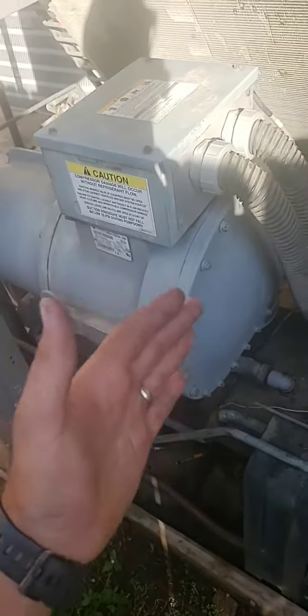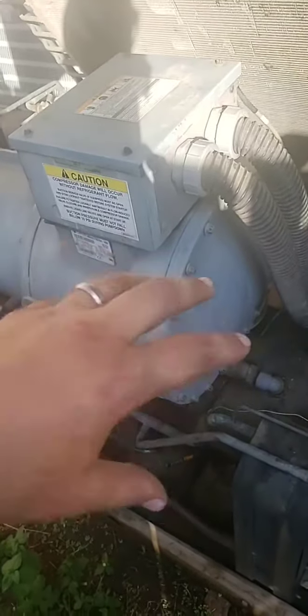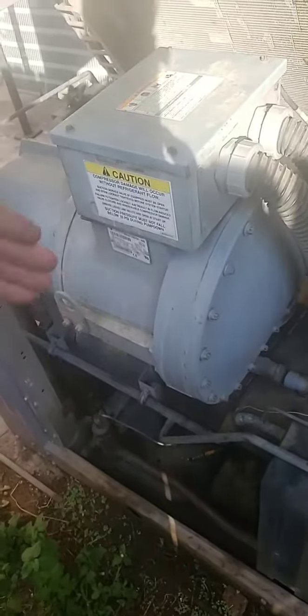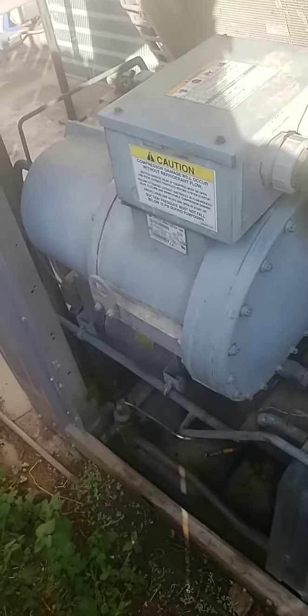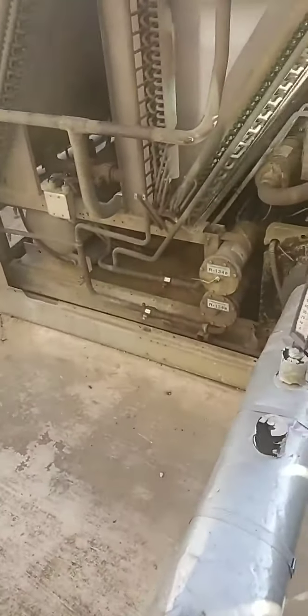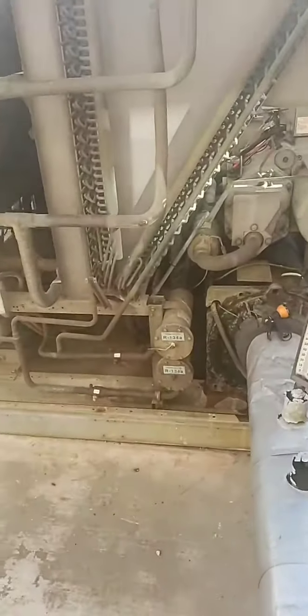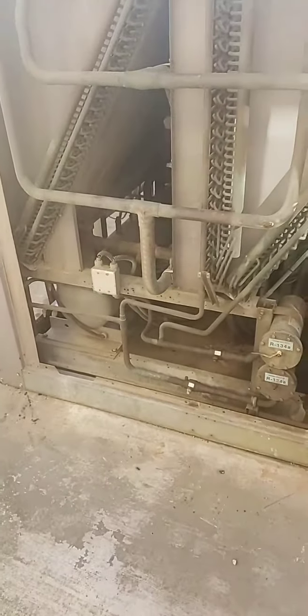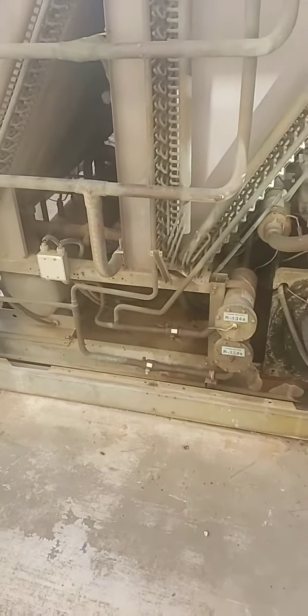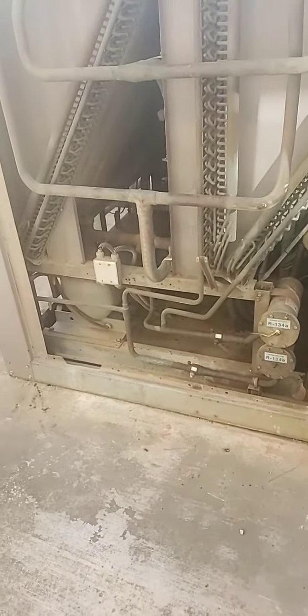And so as that slide moves over, at full capacity, this compressor is not going to start because it's going to put too much of an electrical load on it, and it's going to trip the safeties. That's a pretty common thing to run into with screws like these. But that is how your unloader runs. So like I said, the compressor starts fully unloaded, and then depending on the conditions of the system, it loads up from there. Now, for me to walk around to where the oil separators are, I'm going to have to get kind of close to the other chiller, so if it gets hard to hear me, let me know, and I'll try to figure something else out.